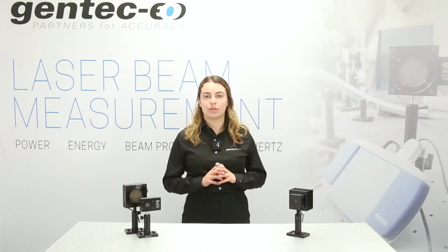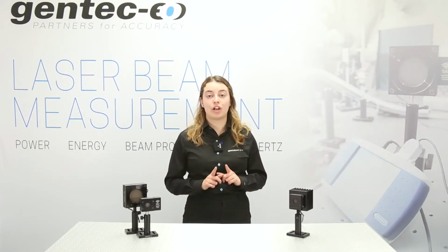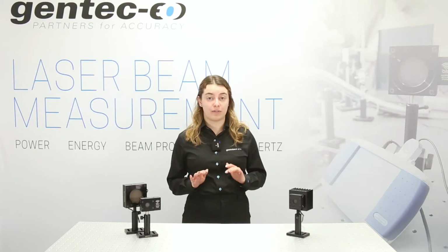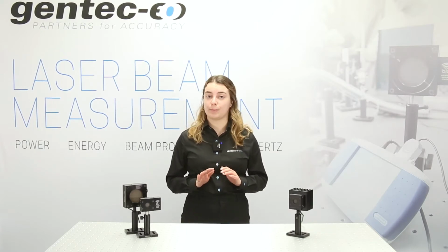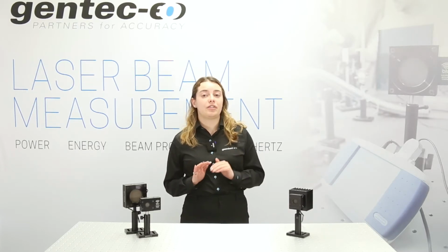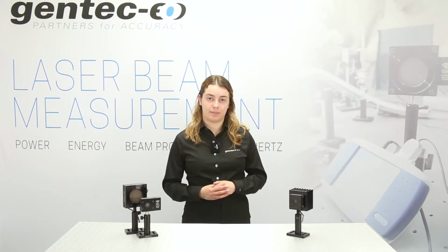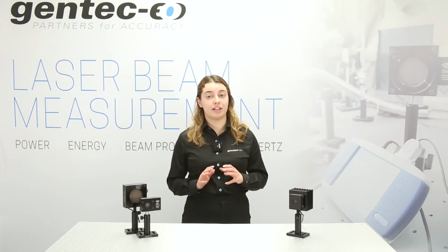This value is used to minimize the effect of spatial nonlinearities that could impact your measurements. The absorption of a detector at a certain wavelength is not perfectly uniform over the detector area. When you use a bigger beam on the absorber, all these nonlinearities are averaged out and you get a much more accurate measurement. The effect of spatial nonlinearities can be more obvious if the beam is not centered on the absorber.